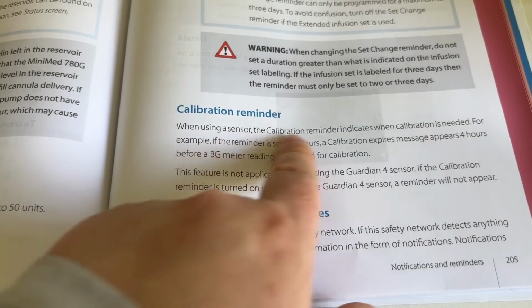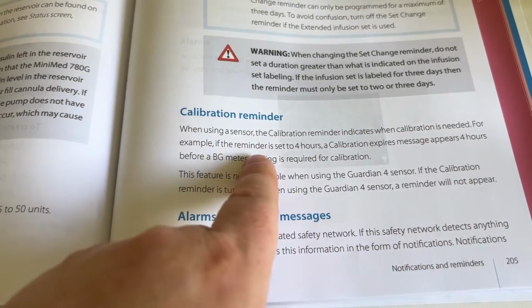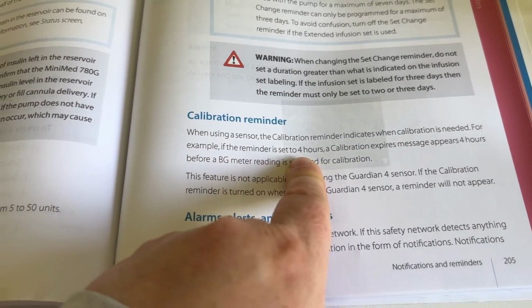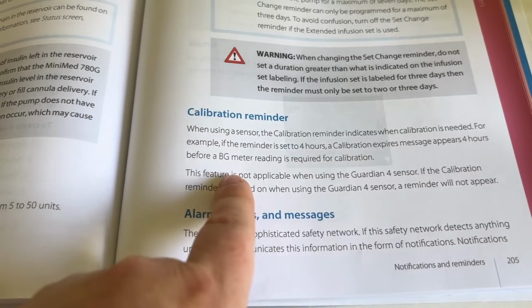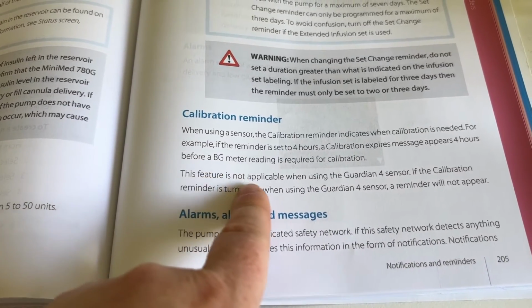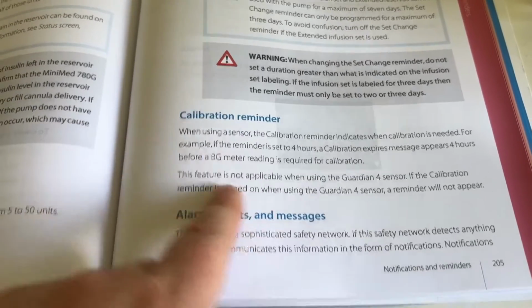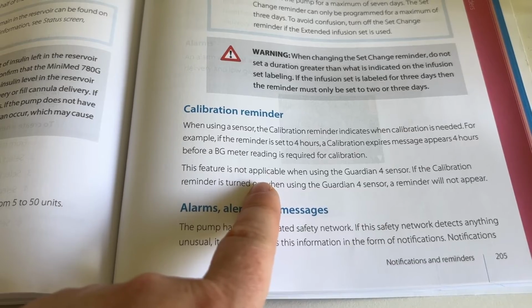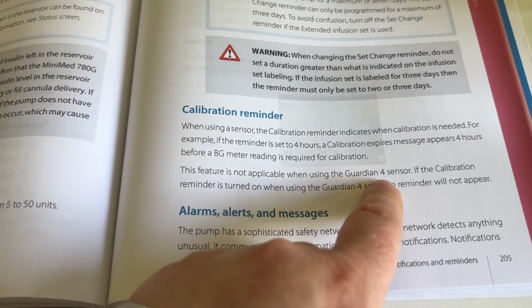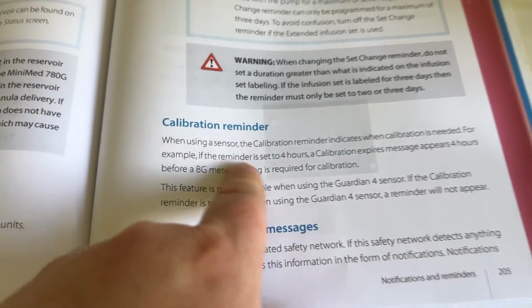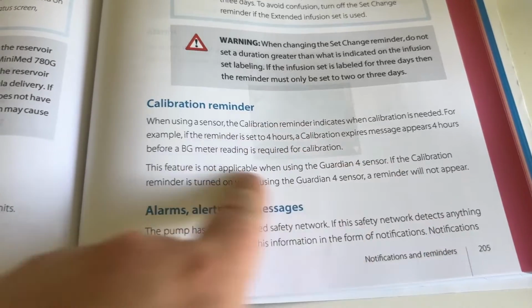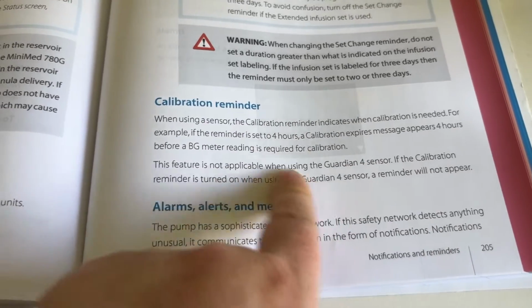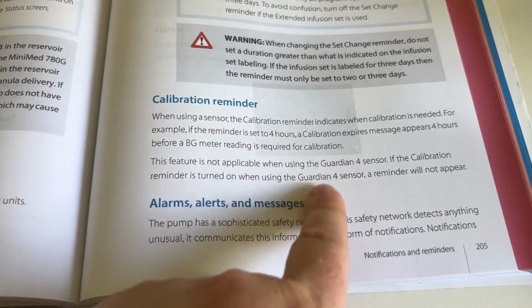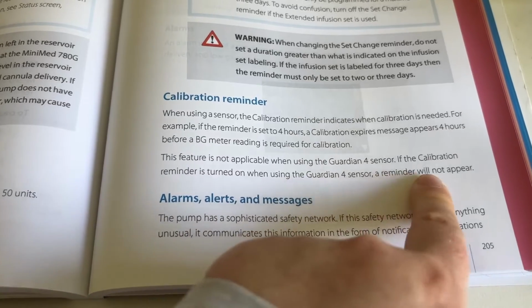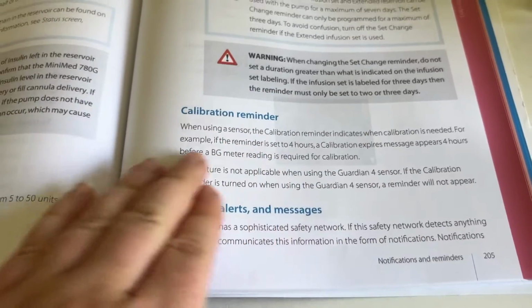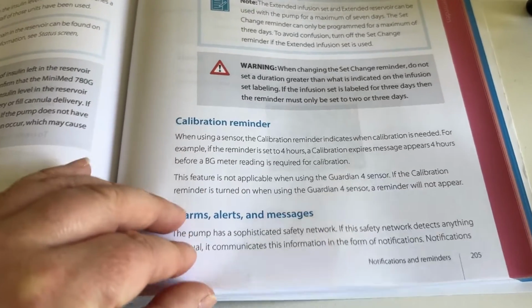And finally, calibration reminder. When using a sensor, the calibration reminder indicates when calibration is needed. For example, you can set it to 4 hours. A calibration expires message appears 4 hours before the blood glucose reading is needed. I feel like these are old things, because look, it says you don't need to do this when using the Guardian 4. So I believe this calibration reminder is probably more applicable for anyone using the Guardian 3, because I believe you had to calibrate that a lot more, and the Guardian 4 doesn't need it, so a reminder will not appear. So you probably will never use that calibration reminder.